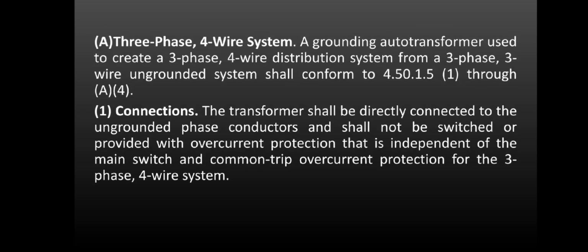A. Three-phase, four-wire system. A grounding autotransformer used to create a three-phase, four-wire distribution system from a three-phase, three-wire ungrounded system shall conform to 4.50.1.5. 1. Connection. The transformer shall be directly connected to the ungrounded phase conductors and shall not be switched or provided with overcurrent protection that is independent of the main switch and common-trip overcurrent protection for the three-phase, four-wire system.